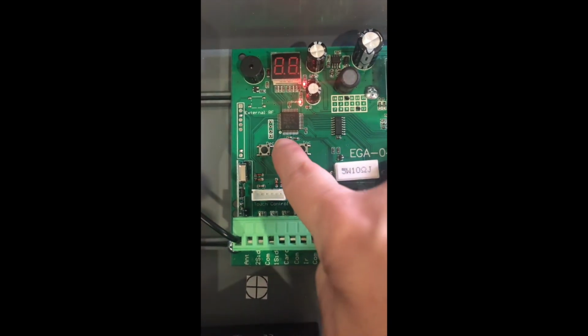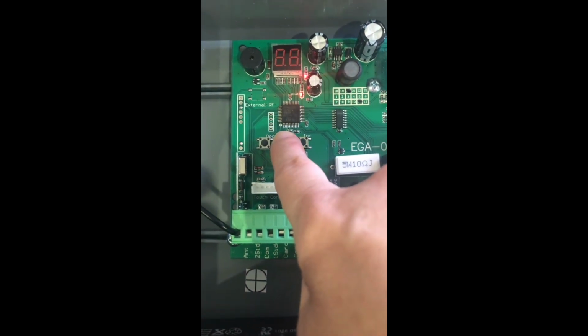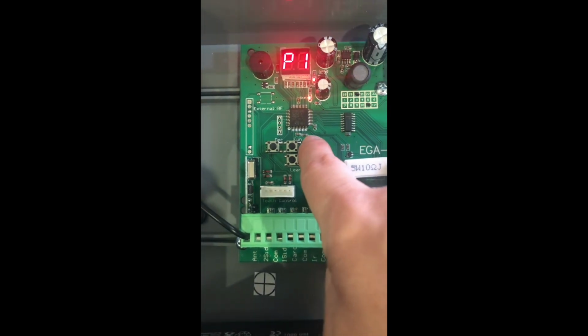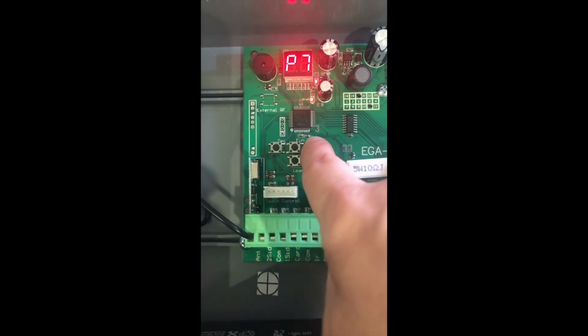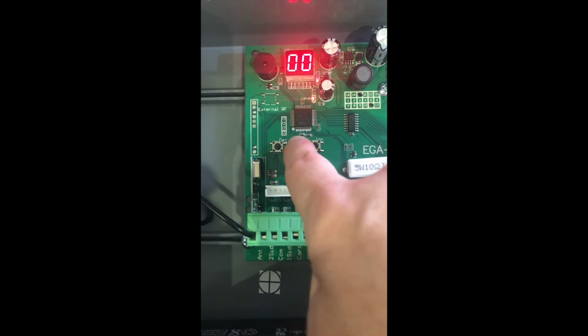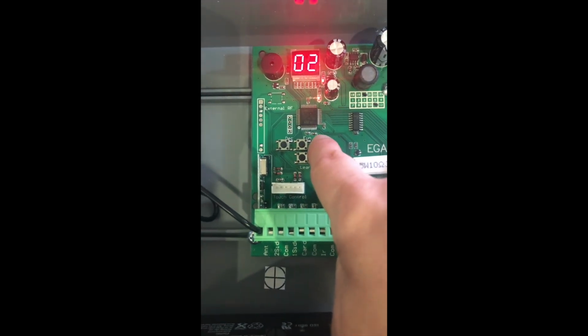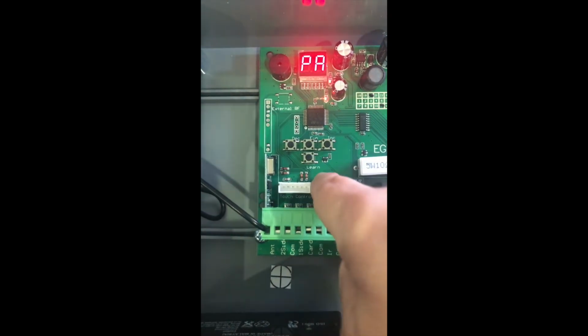Hold the fun button down until PO comes on. Hit the INC button and go up to PA. Hit the fun button to go into the setting. Hit INC to go up to setting 3. Hit the fun button to save and the learn button to get out.